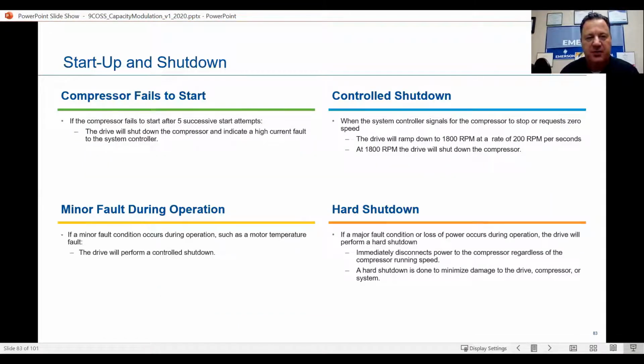Startup and shutdown. The compressor fails to start. If the compressor fails to start after 5 successive start attempts, the drive will shut down the compressor and indicate a high current fault to the system controller. Controlled shutdown. When the system controller signals for the compressor to stop or requests 0 speed, the drive will ramp down to 1800 RPM at the rate of 200 RPM per second. At the 1800 RPM, the drive will shut down the compressor.